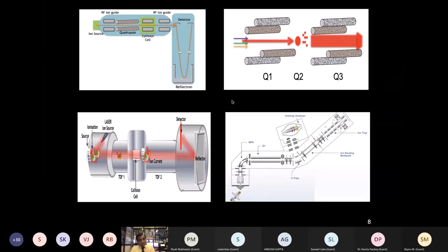And why is MALDI always interfaced with the TOF? Why not have the quadrupole here with multi? If I want to make a new mass spec with multi and quadrupole, why is it not possible, or is it possible? MALDI works on singly charged species, so maybe. You are absolutely right. For the M/Z ratios are very high, the overall mass is very large, and only TOF can accommodate that. Other mass analyzers like quadrupole have a very limited window. They cannot accommodate that. So that's where you see in the other 3 mass specs, quadrupole is there, whereas in the MALDI-TOF, that's not there.